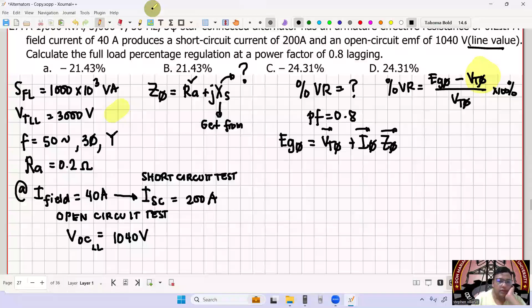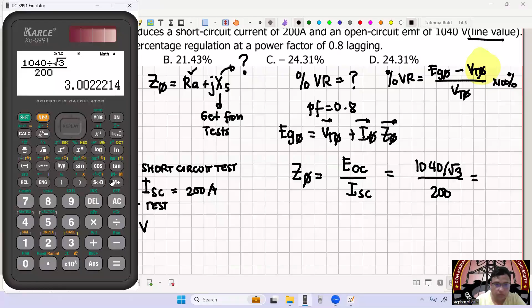Let's first get our Z per phase magnitude. This is now equal to EOC all over ISC. So therefore, this is now equal to 1040 over square root of 3, divided by 200. So 1040 over square root of 3 divided by 200, this is equal to 3 ohms. Why is there a square root of 3? Because the voltage you used in the open circuit test is line to line. So therefore, 3 ohms.